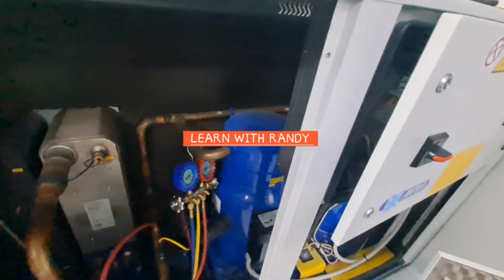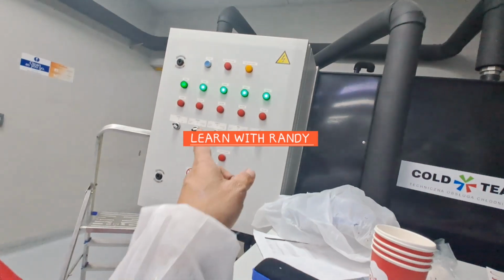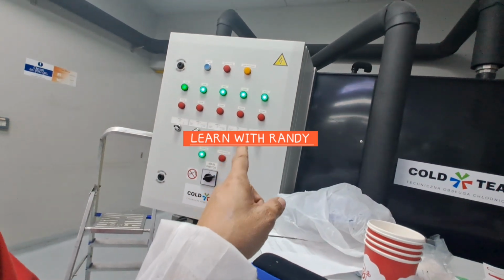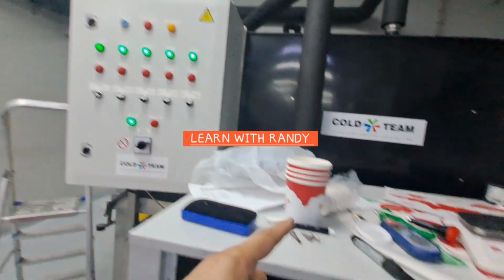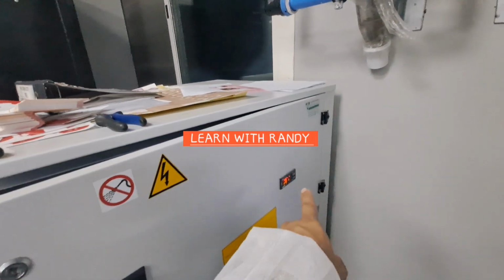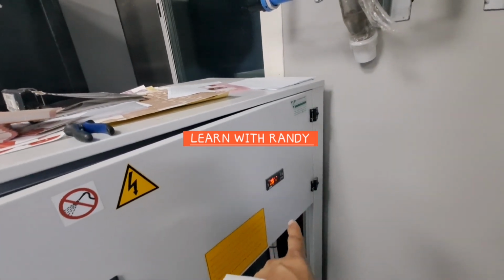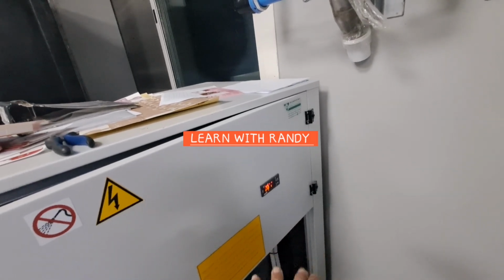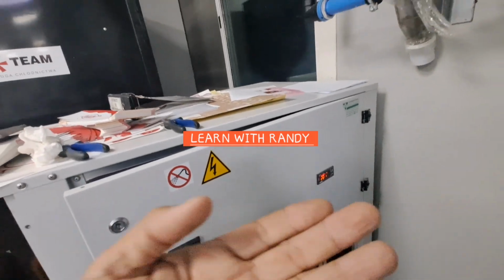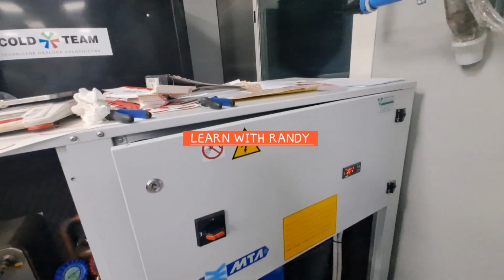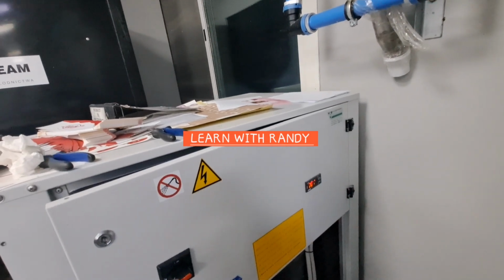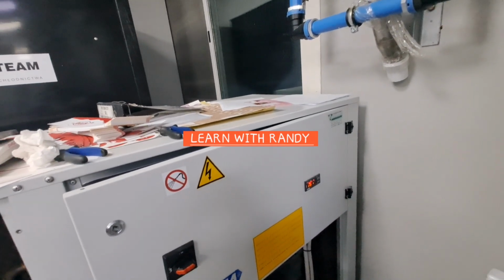Okay, so the controller for the pump, the controller for the fans, and this one controls the compressor and temperature setting. The set point is 4 degrees, 4.5. At 4.5 the compressor will cut off, and on initial start, both compressors will run. When it reaches the temperature, one compressor will go on standby and the other will run continuously to sustain the temperature.